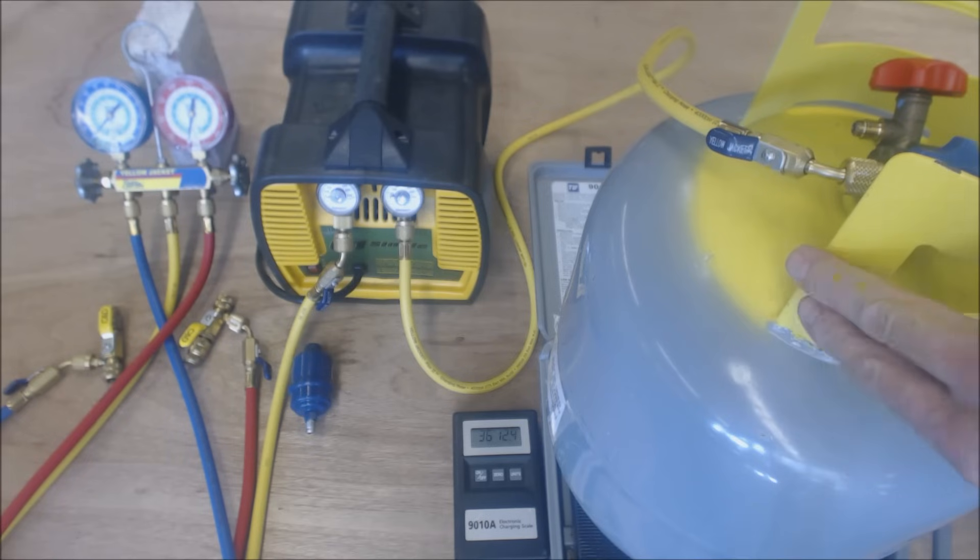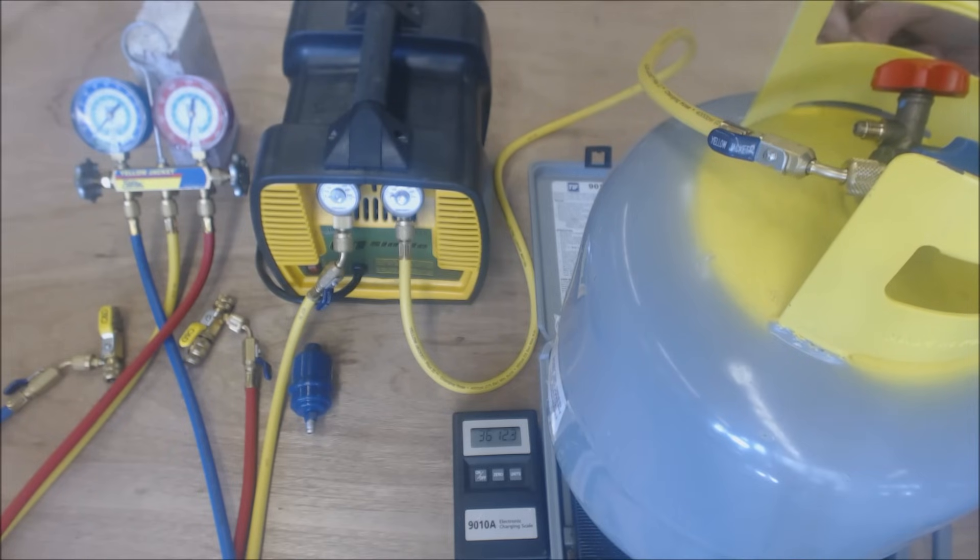On the side of the tank, either right here or right back here, you're going to find a tare weight. A lot of times they're right around 26 to 28 pounds. So you have to find the tare weight. This one actually says 27.9 pounds, so that means about 28 pounds.